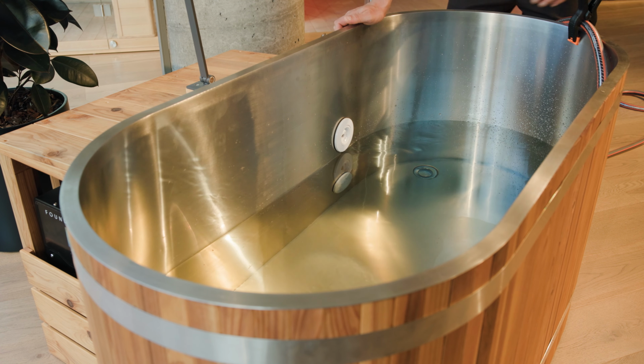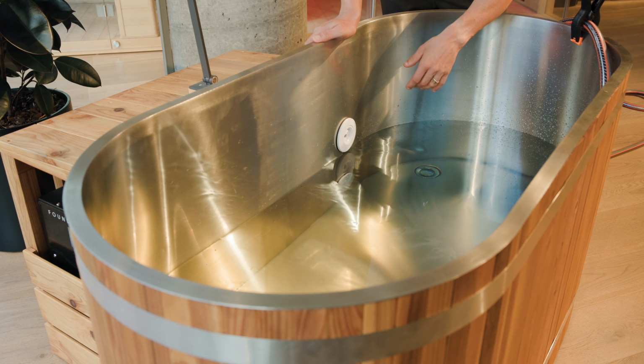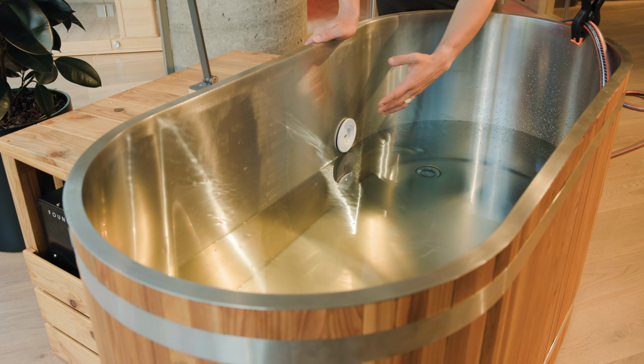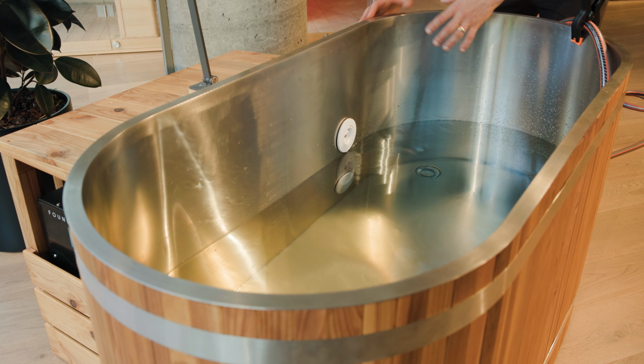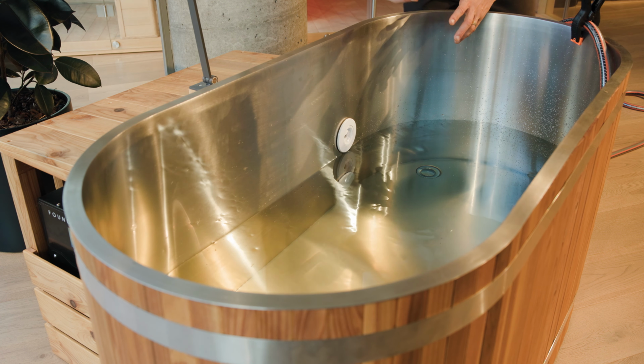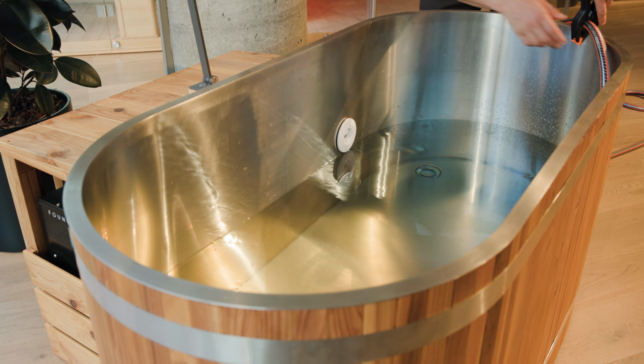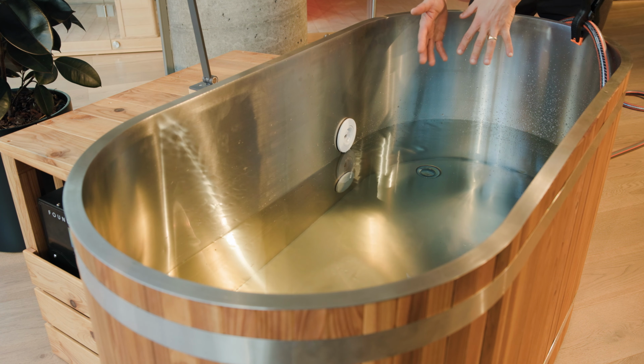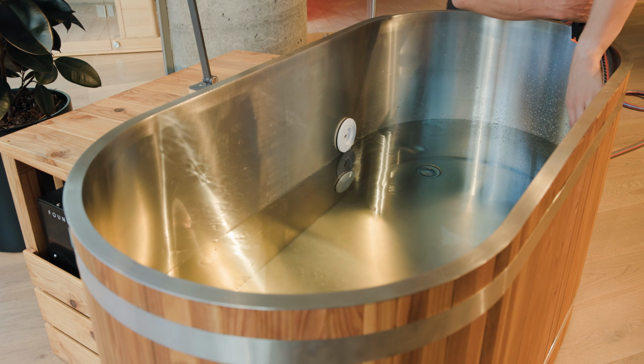Sometimes at this phase, when we turn the chiller on for the first time, it may need to be primed. The reason is when we change the filter, sometimes an airlock can be created inside the chiller, and so we turn the chiller on but it doesn't start pumping out water.